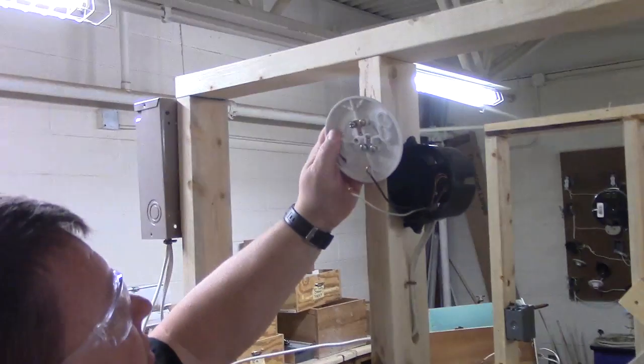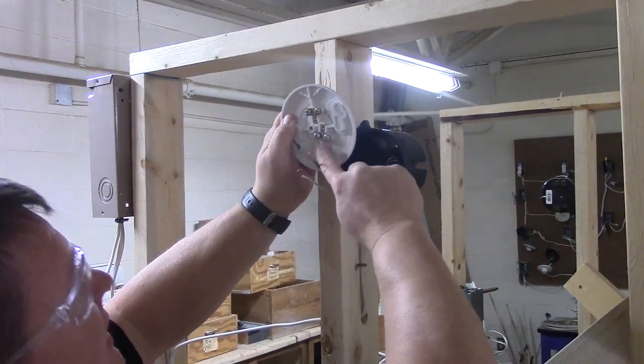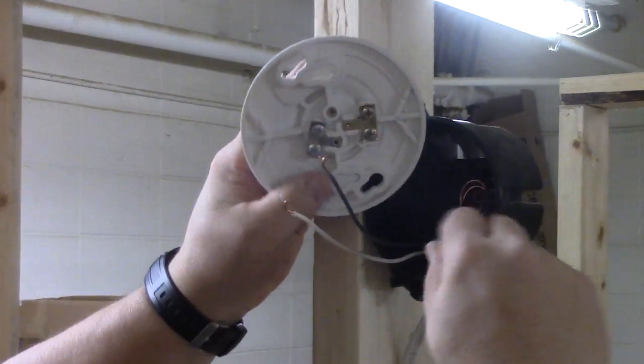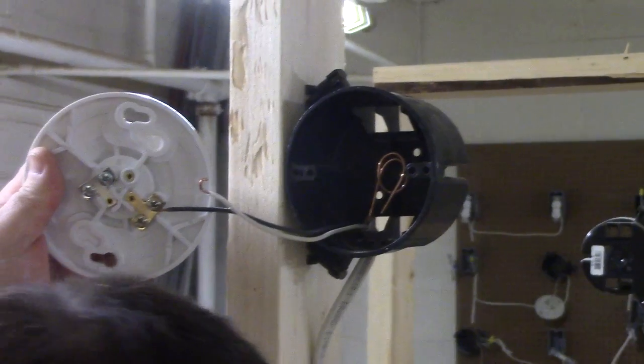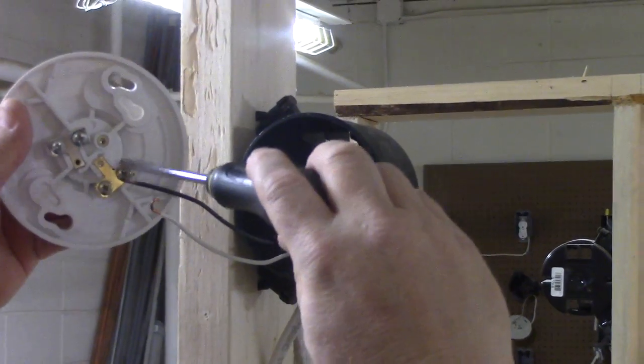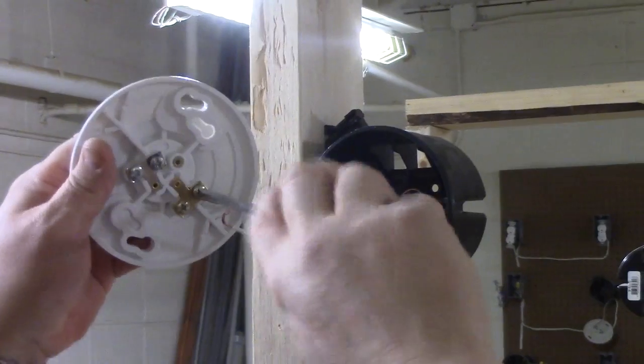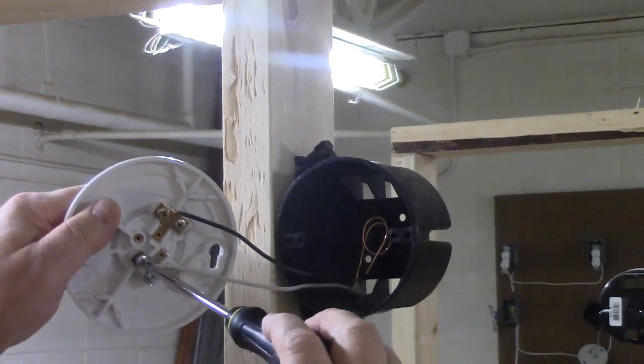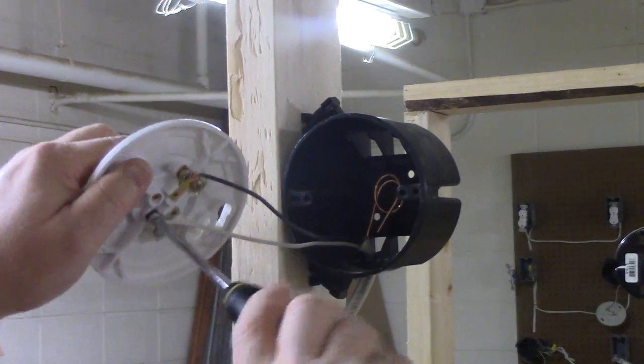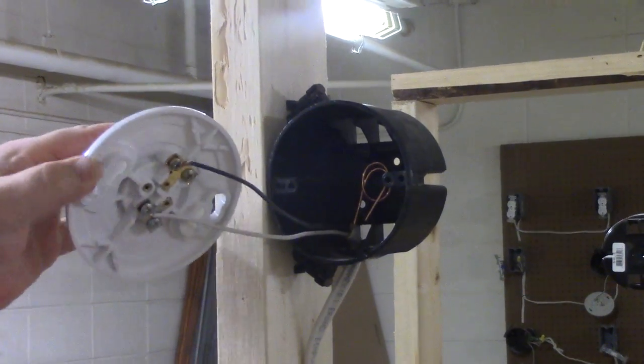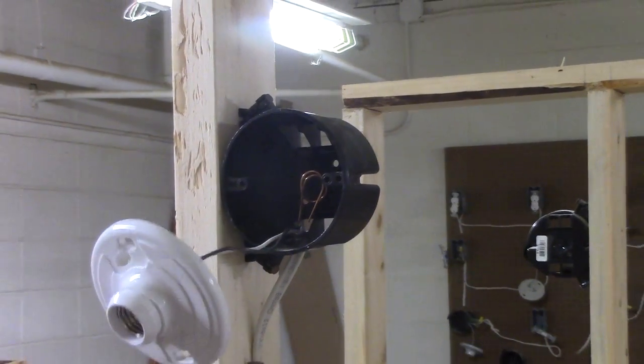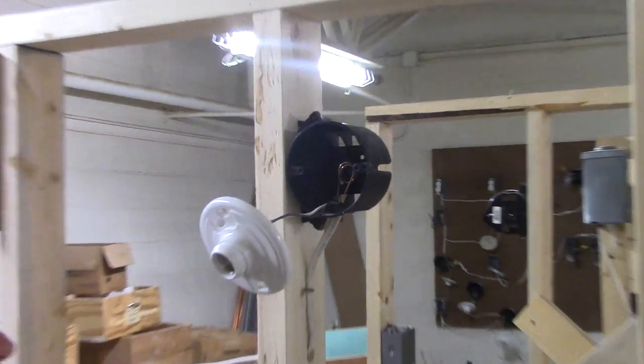Now an easy way to remember this is we have a gold section and a silver section. Our black is going to go to gold and our white is going to go to our silver screw. We want to make sure we are clockwise going on. Same way, turn it around, hook this one up clockwise. We're good there. This is all ready to go into the box and be put on. Put your screws on, mount it up, put your light bulb in it, and you're ready to go.